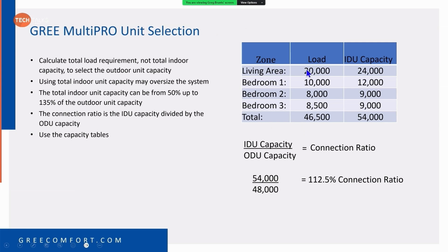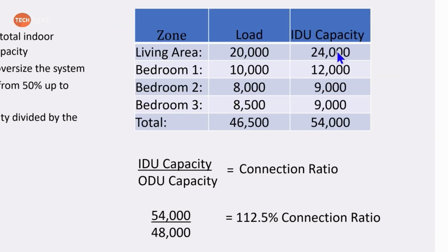If you had a living room, if your load was 20,000, well, we don't have a 20,000 BTU indoor unit, so you go with a 24. Bedroom 1 is 10,000. Well, we don't have a 10,000 BTU unit, so we go with the 12 and so on. So our indoor unit capacity is 54,000 BTUs. We take your 54,000 BTUs divided by a 4-ton outdoor unit. We're at 112.5% connection ratio. We're perfectly fine. We're within the 50 to 135% ratio. So that's where we get them numbers from.